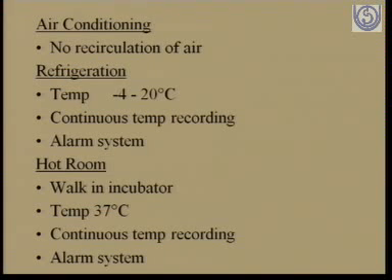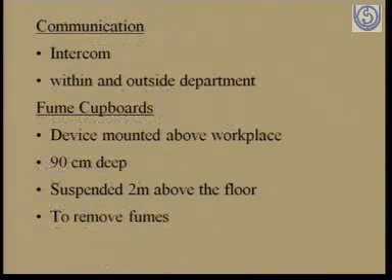Temperature requirement: nowadays there are deep freezers, which are required in molecular biology also, up to minus 75 degrees centigrade, in fact, and with alarm systems. And there is a requirement of calibrating this equipment regularly. Also maintaining the temperature is a must. Walk-in incubator, especially walk-in cooler also, this is a requirement in the laboratories.